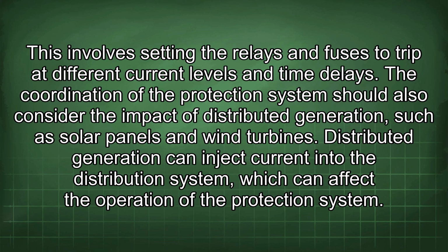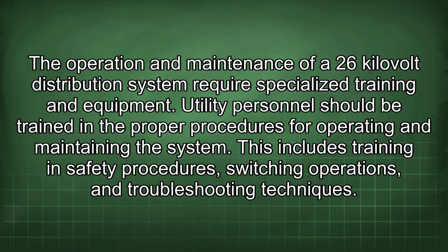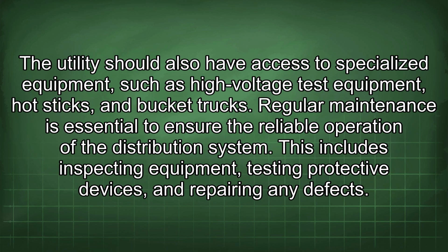turbines. Distributed generation can inject current into the distribution system, which can affect the operation of the protection system. The operation and maintenance of a 26 kilovolt distribution system require specialized training and equipment. Utility personnel should be trained in the proper procedures for operating and maintaining the system. This includes training in safety procedures, switching operations, and troubleshooting techniques. The utility should also have access to specialized equipment, such as high-voltage test equipment, hot sticks, and bucket trucks.